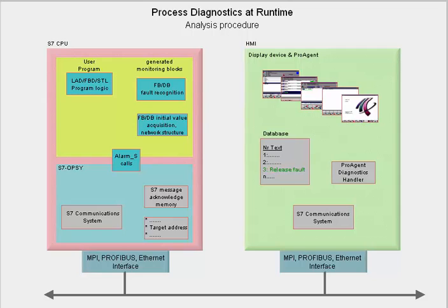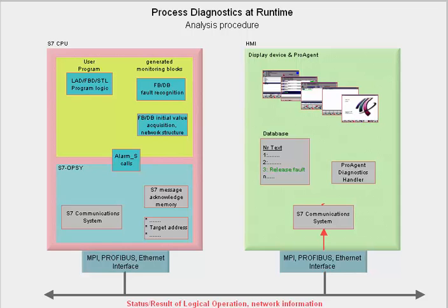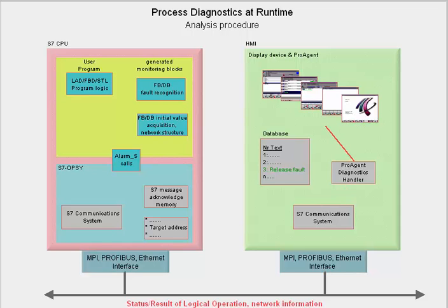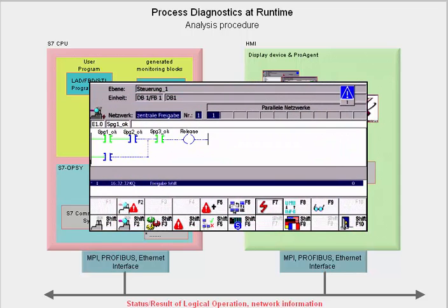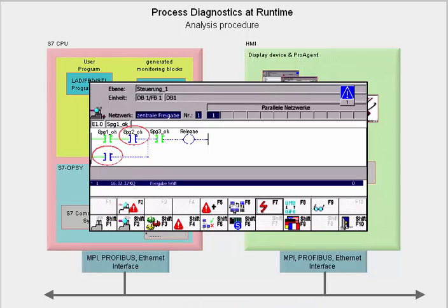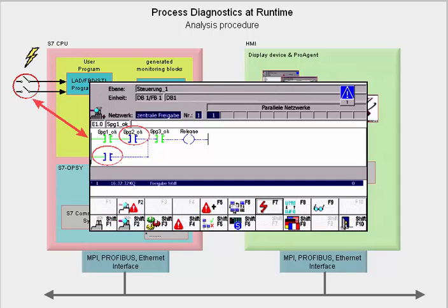A message with this content is then sent back to the requesting HMI device and on the corresponding mask is displayed as a signal list, ladder diagram or statement list detail network with indication of the faulty signals. From this, the operator can now determine which signals caused this fault state without having to use a programming device.